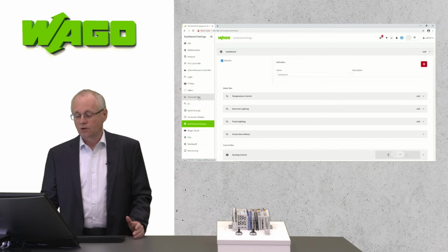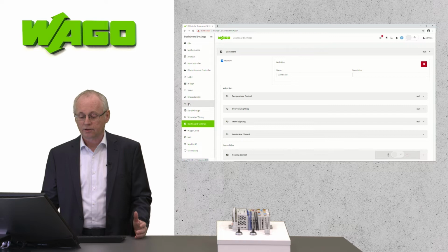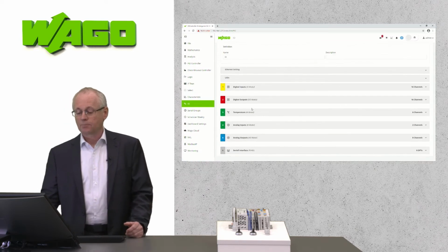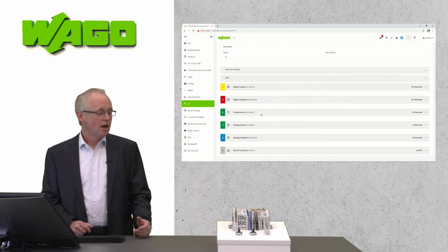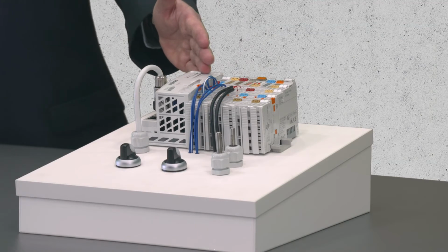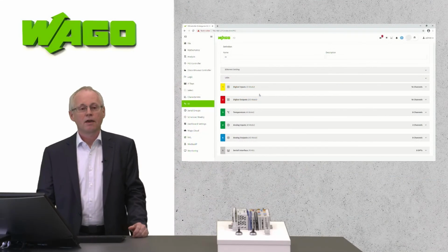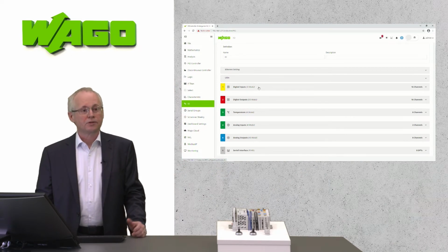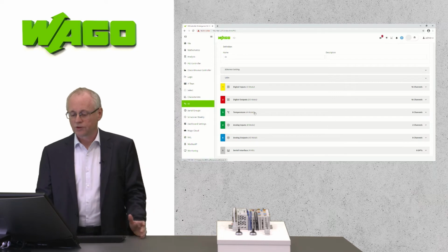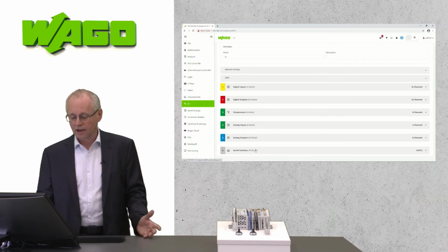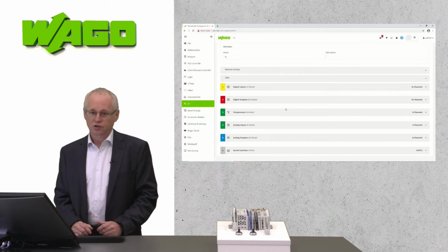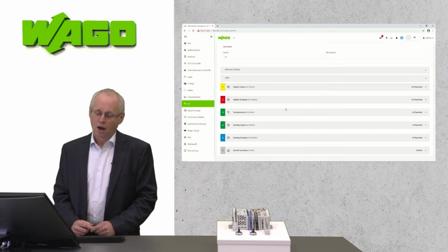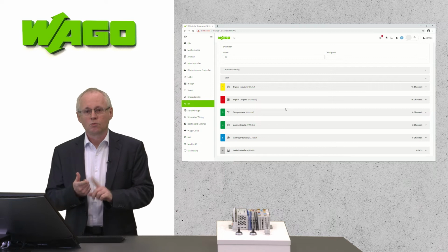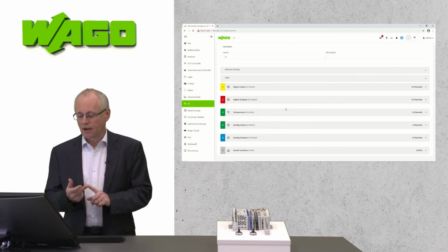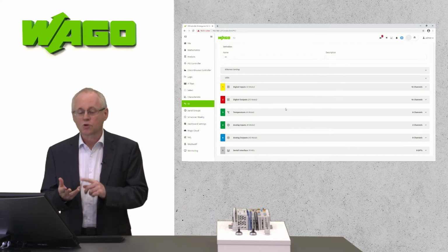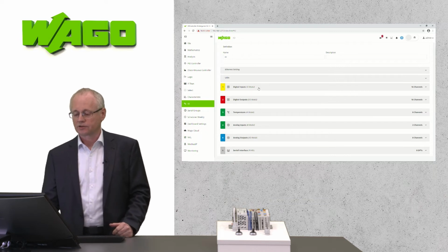If you start to configure a new application, you will usually start with the IO configuration, and the application automatically recognizes which kind of modules are connected to the controller, and the list of modules is displayed here. In this example, we have a digital output module, a digital input module, two different temperature modules, an output module, and a serial interface. For our temperature loop, we need different data points. One is a release signal, one is a room temperature signal, a set point, and also an output to control the heating valve. So we will start with a digital input with a release signal.